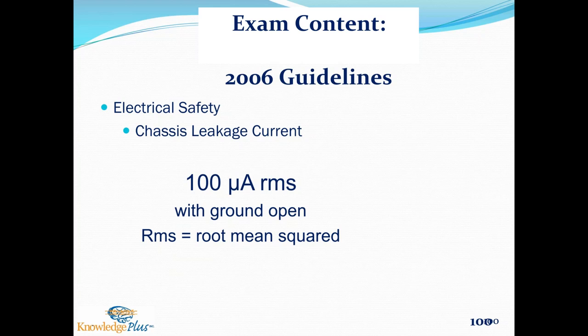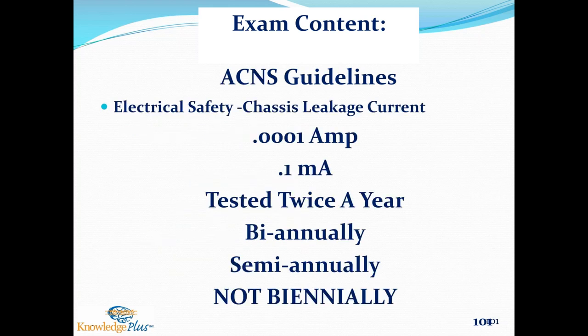Twice a year, you have to get your equipment checked by Biomed. And what they're checking is the chassis leakage current. And in the guidelines, it states that that leakage current shouldn't be more than 100 microamps RMS with ground open. Now, they might have that number on your exam. They might have it in amps, milliamps, or microamps. So be ready to answer in the unit that they give you.